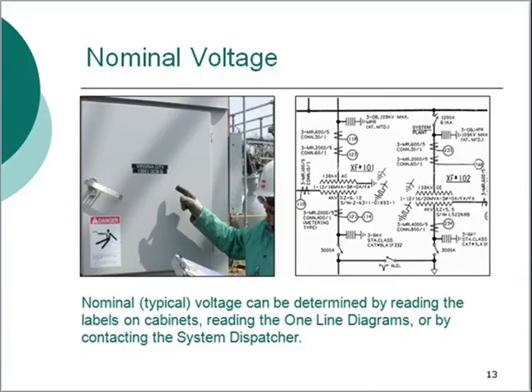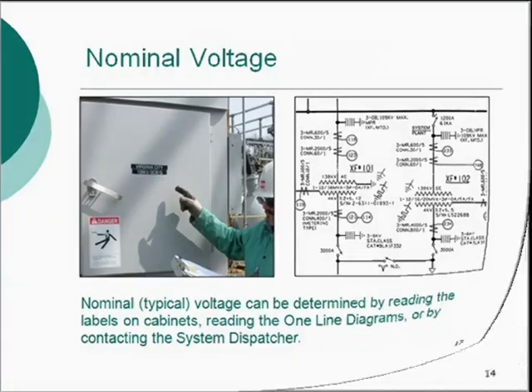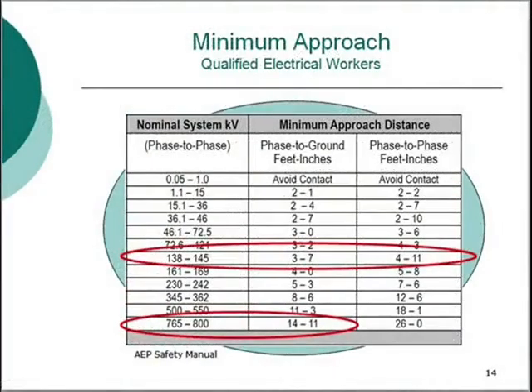Knowing the nominal voltage is fundamental to determining minimum approach or safe working distances. The higher the voltage level, the greater the minimum approach distance. For example, the minimum approach distance for 138 kV is 3 feet 7 inches phase to ground and 4 feet 11 inches phase to phase. Qualified electrical workers understand this terminology and the application of minimum approach distances. For all others entering a substation, maintain a distance of at least 15 feet from energized lines. Notice on the chart that 15 feet is a safe working distance for even the highest substation voltages.